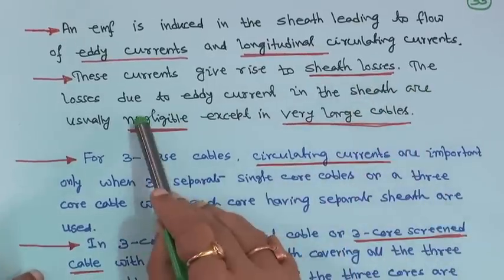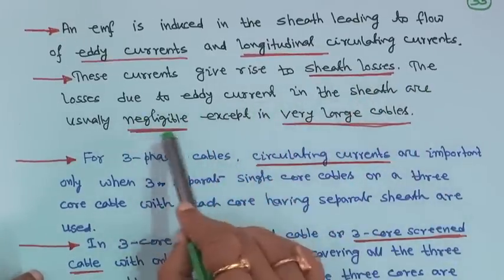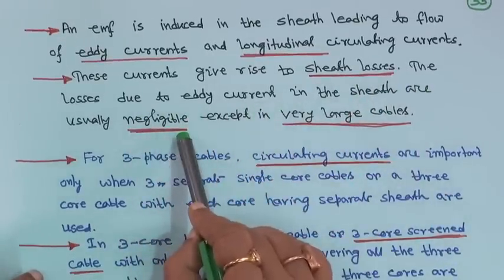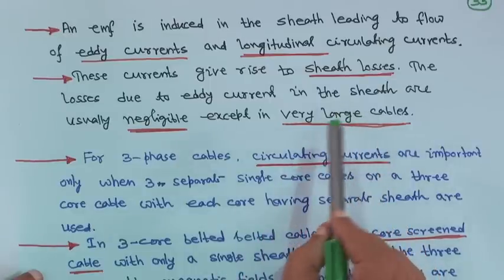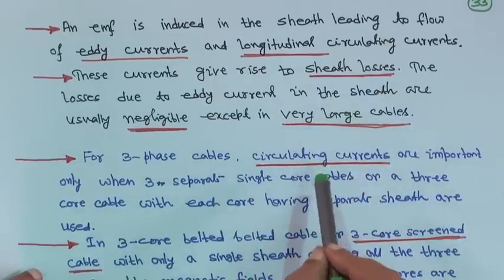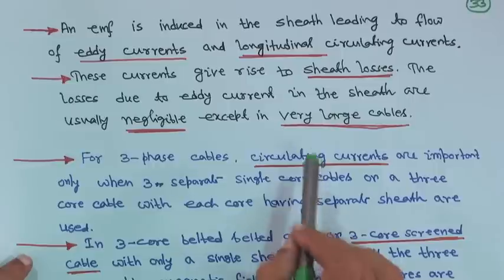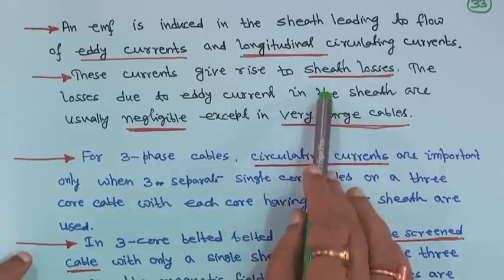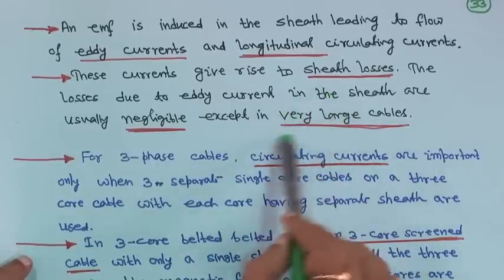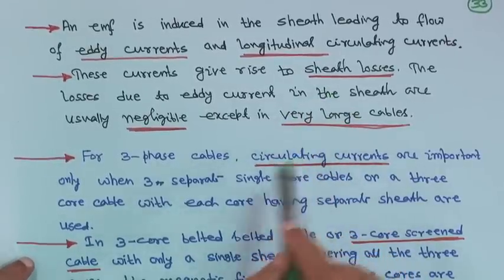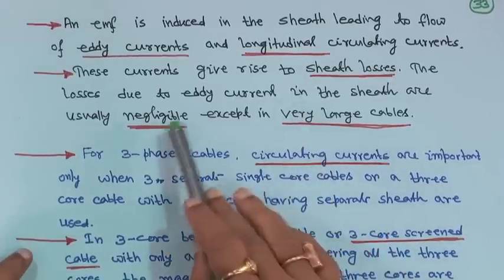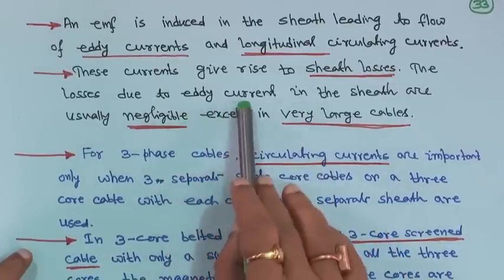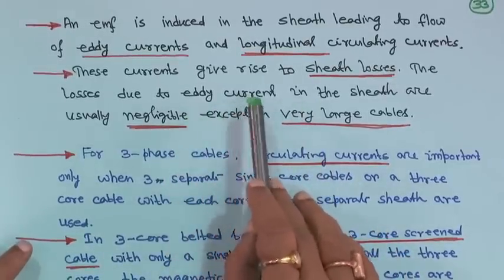The losses due to eddy current in the sheath are usually negligible except in very large cables — meaning high voltage 3-phase cables — or very long cables in terms of kilometers. Otherwise, that eddy current loss is negligible.